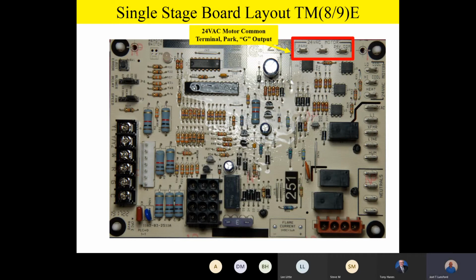The other thing about all ECM high efficiency motors, whether it's a standard ECM motor like what we're talking about here, or if it's a variable speed motor, they all have the same function I'm about to touch on. And that's this. Not only do they just sit there with power all the time, like we talked about, waiting for a 24 volt command, in addition, if they have more than one 24 volt command, in other words, you could have several commands going to that board, or to that motor. You could have a low cool, you could have a high cool, you could have, if it's on a heat pump, an auxiliary heat command, and so on. So that motor may be receiving more than one 24 volt speed command.